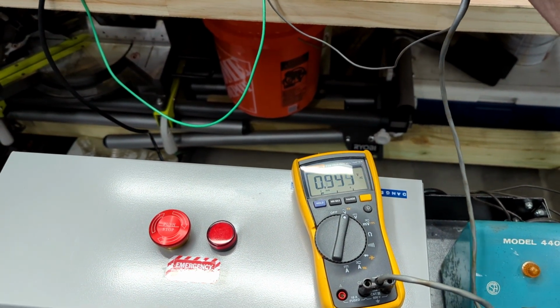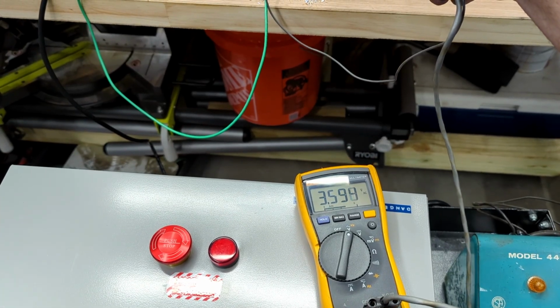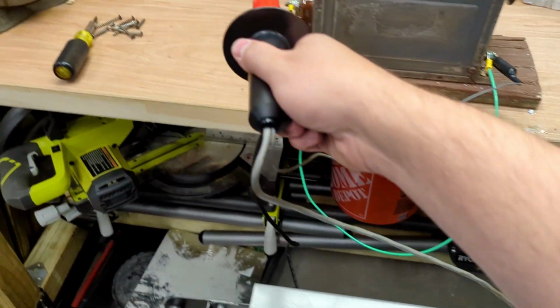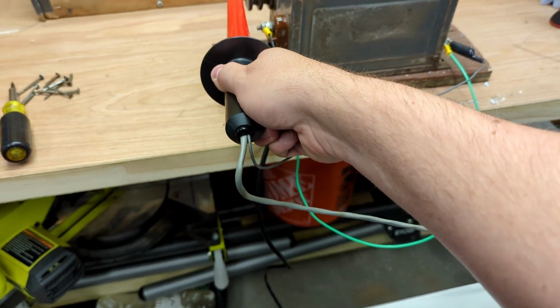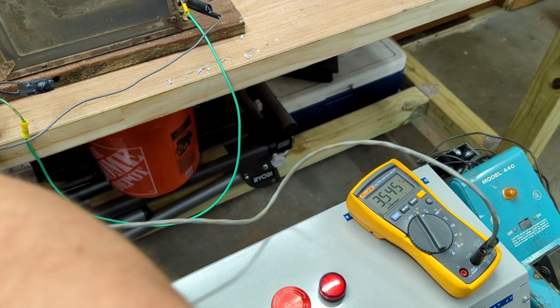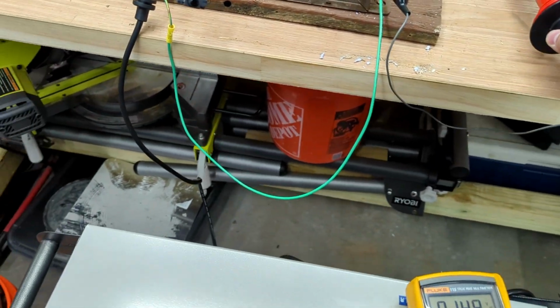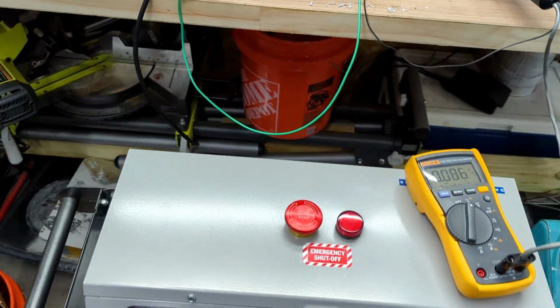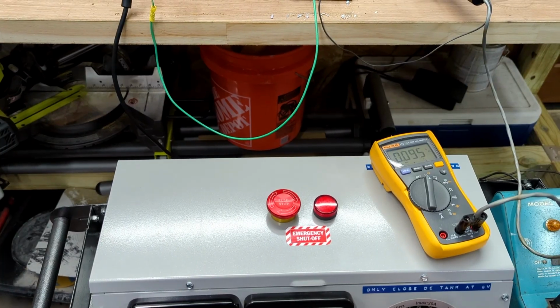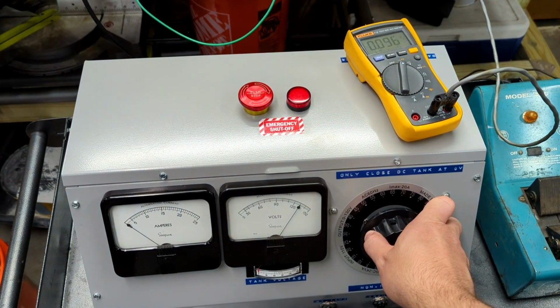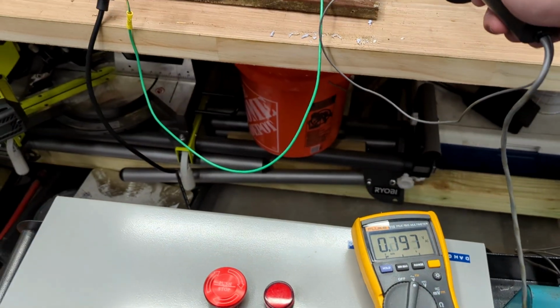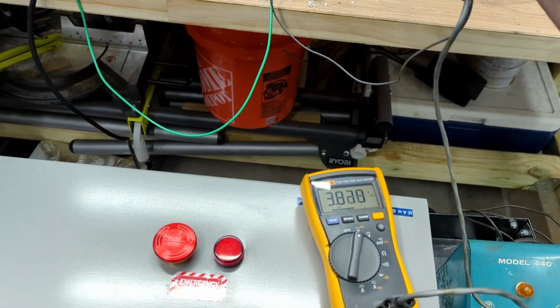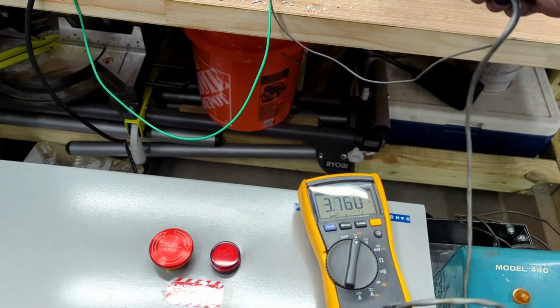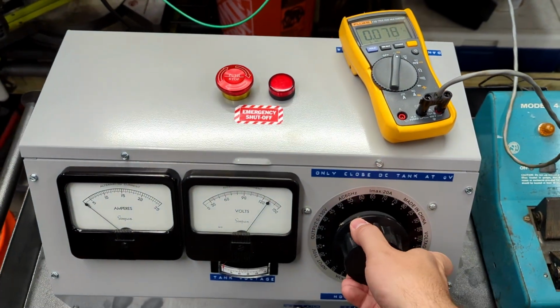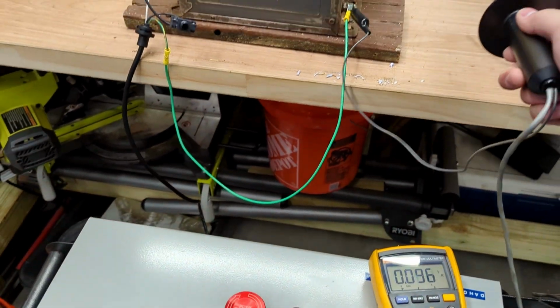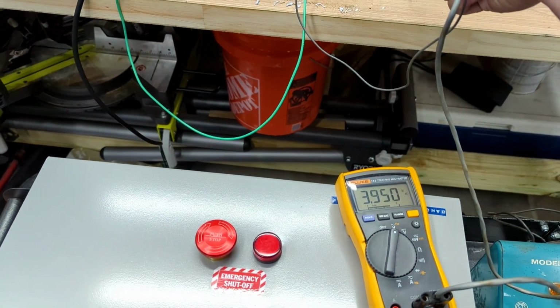3.5. I feel a good hum coming through that transformer there. This side. 3.5. Good. Okay, so that means 7 kV right there. Let's bring this up just a bit. Drive it up just a little further. This is supposed to be about 9 kilovolts, but there you go. 3.8. Let's go a little higher. Sometimes you've got to drive a little hotter to get the actual rated 9 kV.